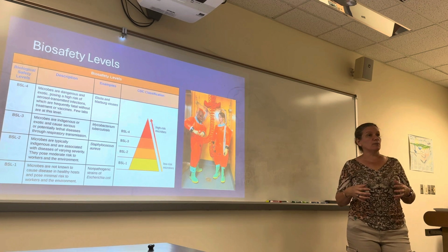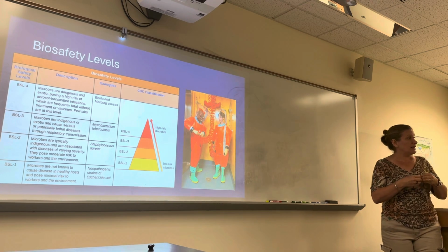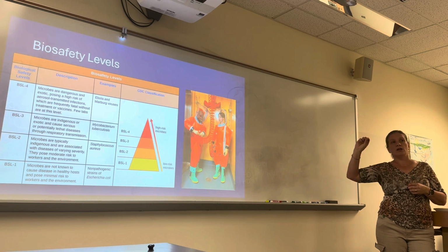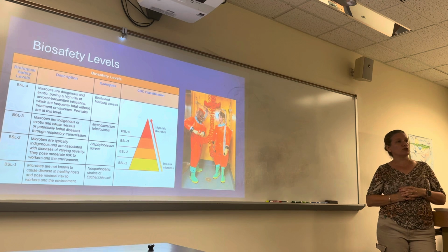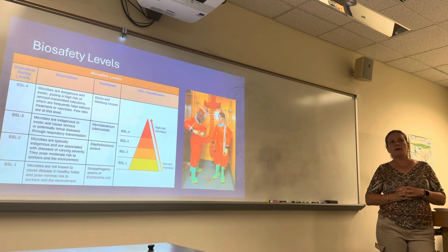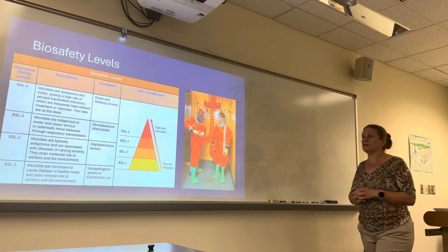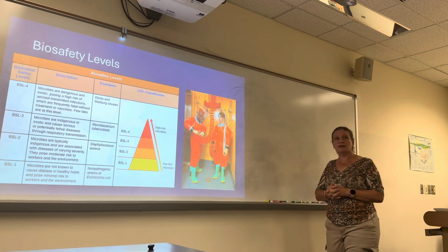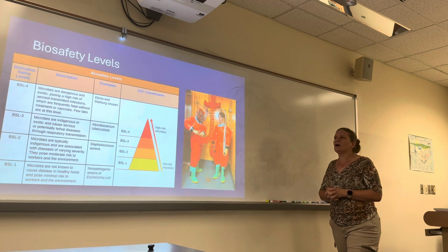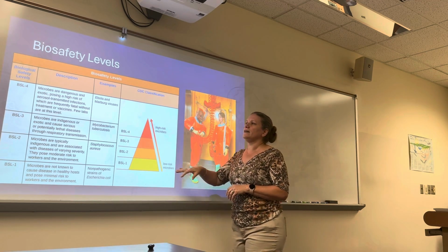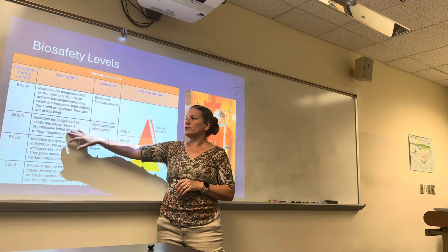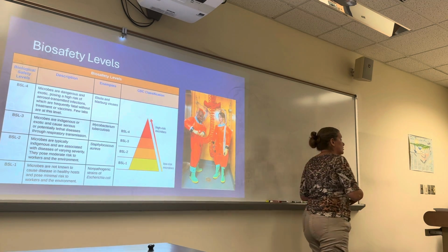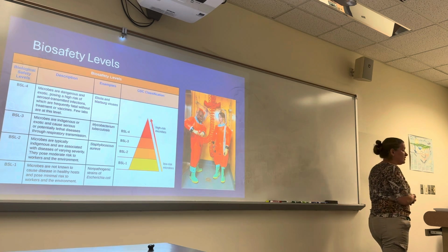So in case anything becomes aerosolized, it's going to stay in the room and go out of the room through a specific route that's going to allow it to go through filters to remove any organisms that might have been aerosolized during the process of working with it in the laboratory. Biosafety level 3, now we're looking at the organisms that are going to cause more serious or potentially lethal diseases. In this case, you're going to start working in a biosafety cabinet.